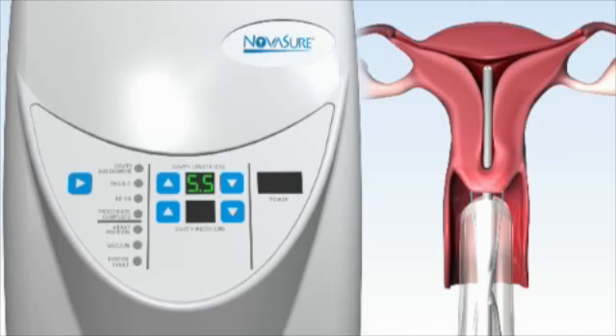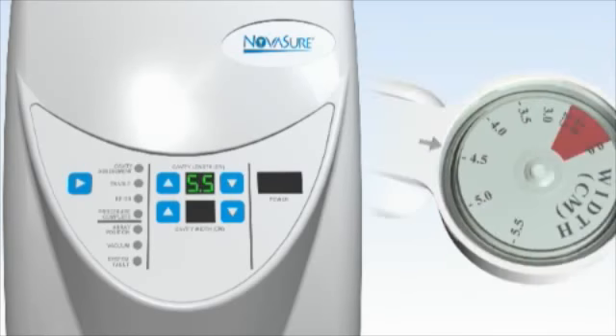When proper placement has been achieved, a cornu-to-cornu width measurement will be obtained from the width dial. Key the value indicated on the width dial of the NovaSure disposable device into the NovaSure RF controller width setting by depressing the up and down arrows. The width of the cavity should be at least 2.5 centimeters before proceeding.